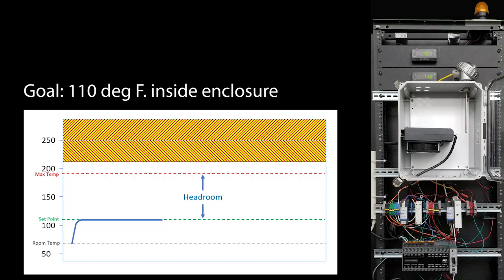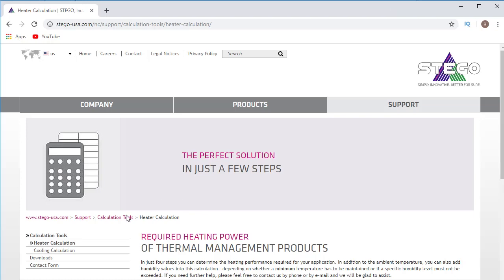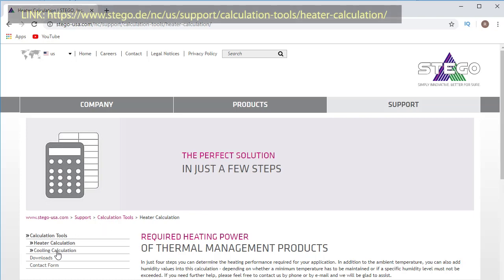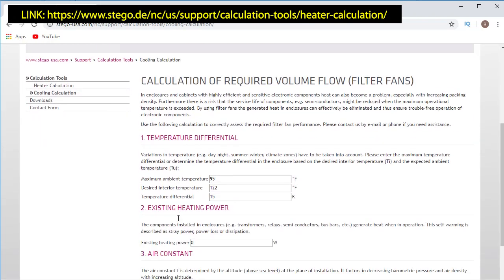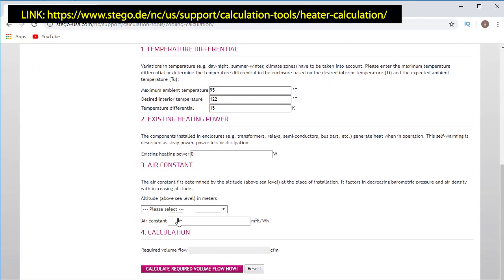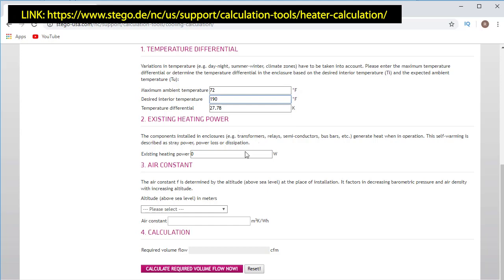Given that, we just go to this awesome tool on the Stego enclosure's website and select cooling. My room temperature is going to average around 72 degrees. I want the internal box temperature to be around 190 degrees max and I have a 500 watt heater in the box.